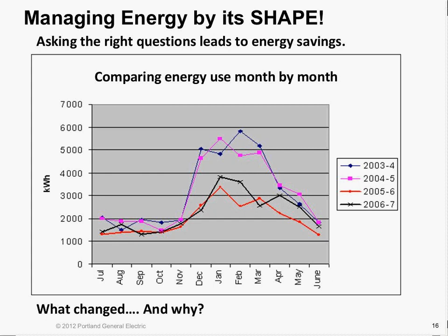In this case, you can see that I put December in the middle of the chart because that is the highest bill, and I wanted the winter, which is where you get a lot of the heating load, to be in the middle of the chart rather than January through December. So the winter is in the middle. And what you've got here is 2 winters that were very high. I'm learning to draw with this thing. It's fun.